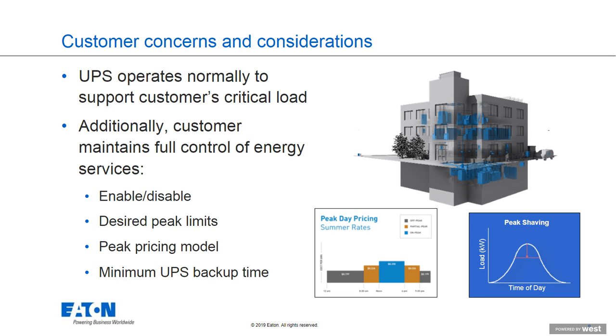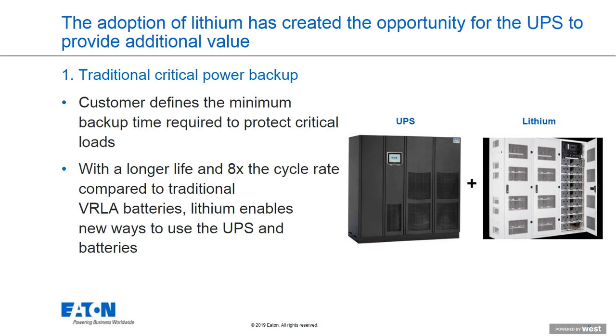Their peak pricing model also comes into play—if there's time-of-day or time-of-use rates in effect, that pricing model from the utility can be programmed in, so the customer can say this is when I want to act as a distributed energy resource, and during this part of the day maybe I don't. They always have ultimate control, and of course the user sets the minimum amount of battery that must be maintained to support the data center. If there's extra capacity, fine, but the minimum is under the end user's control.